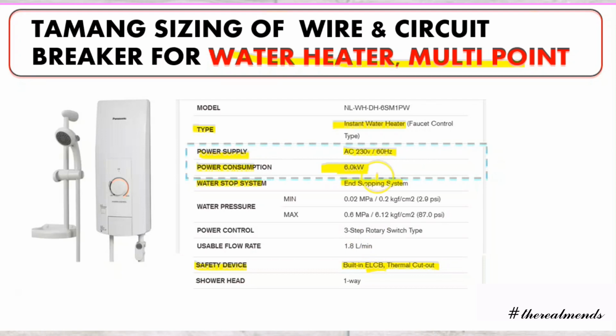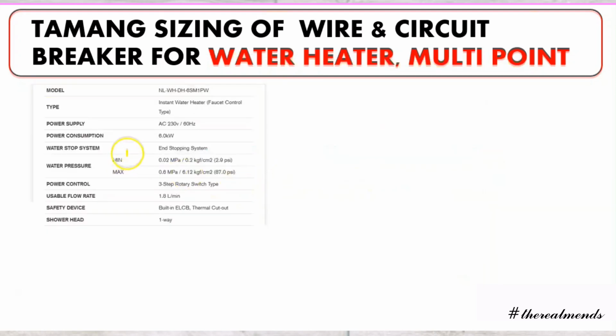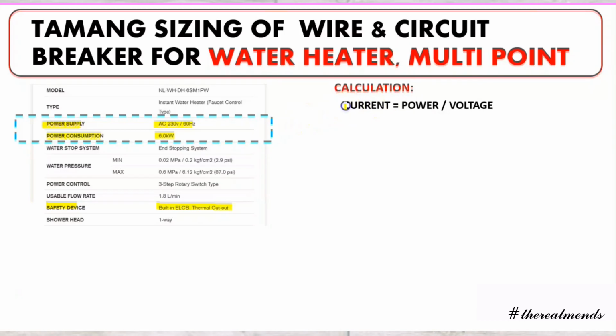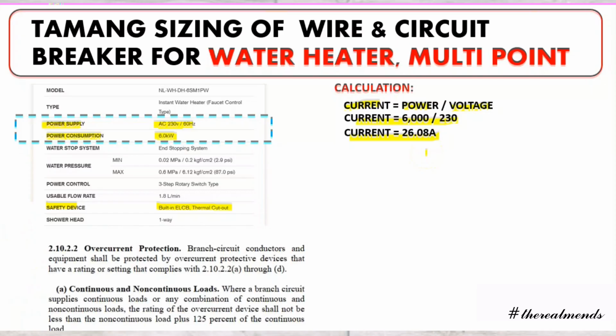To start with the calculation, let's focus only on the electrical side. Power supply, 230 volts, single phase, power consumption of 6 kilowatts. Its safety device is an earth leakage circuit breaker, ELCB. We all know the current is the power, 6 kilowatts, over the voltage, 230 volts. If you compute 6000 over 230, you have 26.08 amperes.